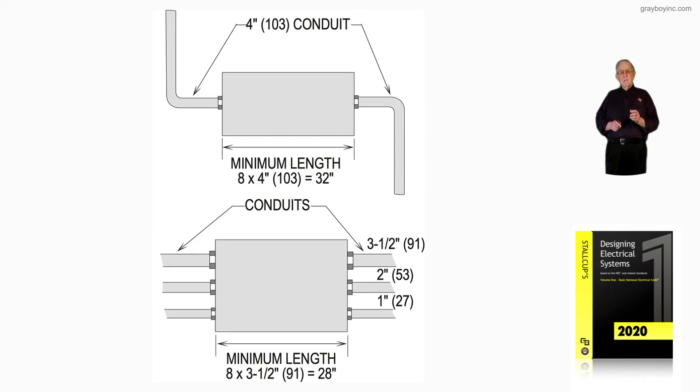But since the conductors are number four or larger, it's the size of the conduit where it's a straight angle or U-type pull. So this illustration is illustrating a straight pull based upon 314.28A.